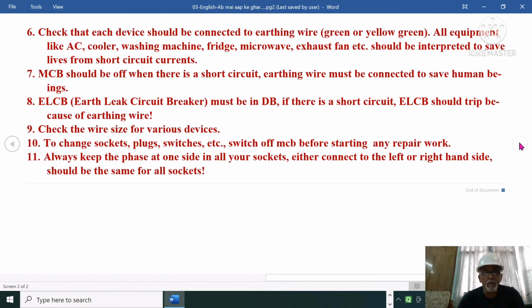Now, this is ELCB. Beside it is the MCCB, molded case circuit breaker, that is the main circuit breaker. From outside, from the meter, the phase and neutral come to that. This is the earth leakage circuit breaker with the main breaker in the DB. If there is a short circuit, ELCB should trip because of the earthing wire. Now, if ELCB is there, what will happen if someone tries to use earth as a neutral to light up something, to start something? The ELCB will never allow it. It will trip itself. It will not allow you to do wrong work.